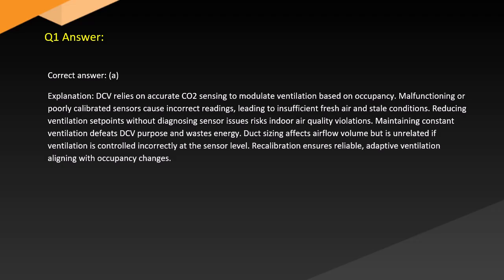Answer. Correct answer: A. Explanation. DCV relies on accurate CO2 sensing to modulate ventilation based on occupancy. Malfunctioning or poorly calibrated sensors cause incorrect readings, leading to insufficient fresh air and stale conditions. Reducing ventilation set points without diagnosing sensor issues risks indoor air quality violations. Maintaining constant ventilation defeats the DCV purpose and wastes energy. Duct sizing affects volume but is unrelated if ventilation is controlled incorrectly at the sensor level. Recalibration ensures reliable, adaptive ventilation aligning with occupancy changes.